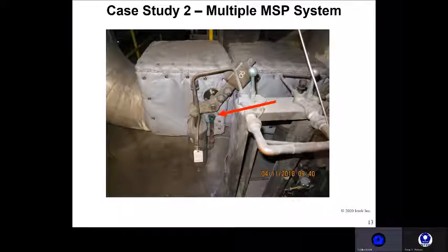Armed with this information, during the leak audit using the helium leak detection equipment and tracing lines from the east side of the condenser, we found several uncapped pipes. It was discovered that during the maintenance outage a few months prior, the extraction steam check valve shown here had the packing replaced with a different gland that no longer required drain lines. The now obsolete drain lines were not plugged, allowing approximately 30 SCFM into the condenser.